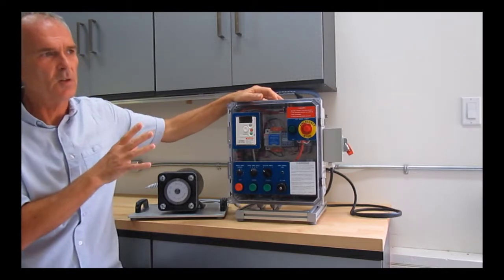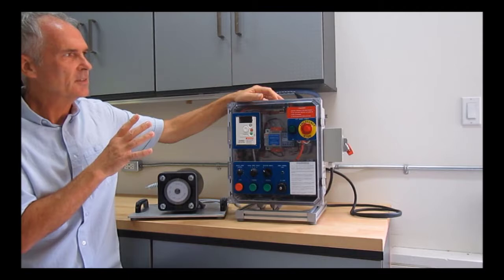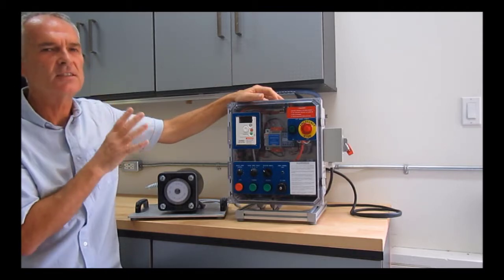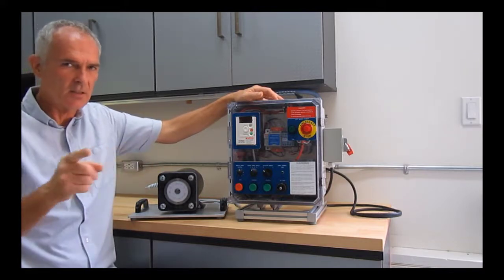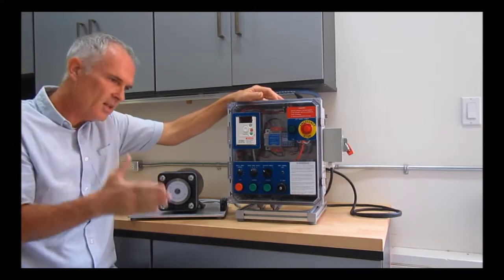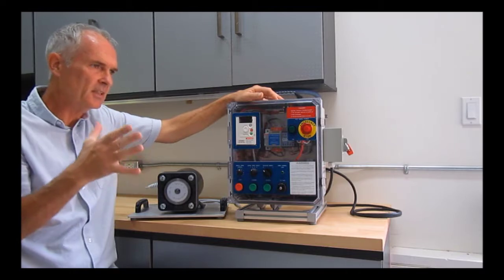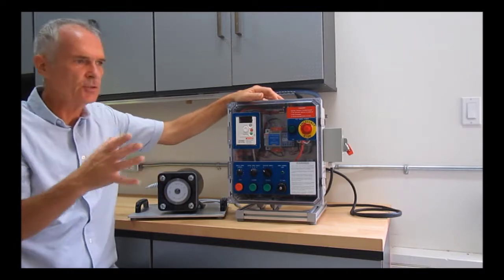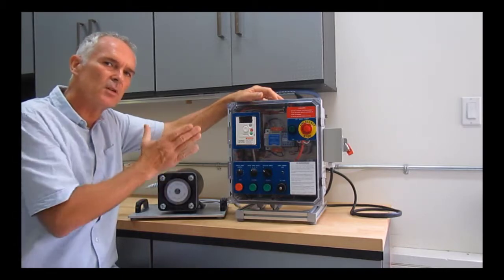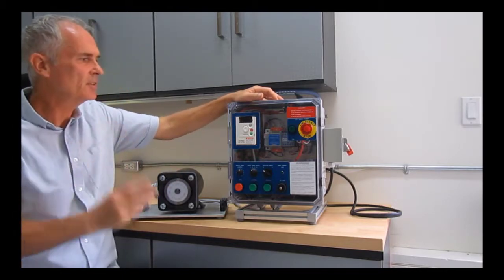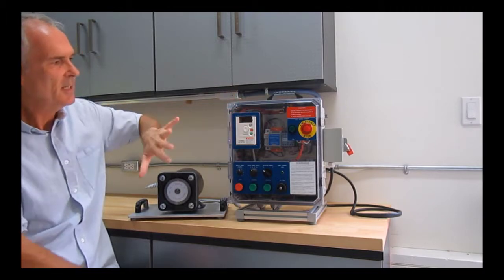Lastly, the third mode is what's called performance mode. We can set it to performance mode, which is what they call constant torque. Constant torque is used in metal turning, metal cutting, crushing, extruding applications where you need a constant torque through the whole operating range of the motor.